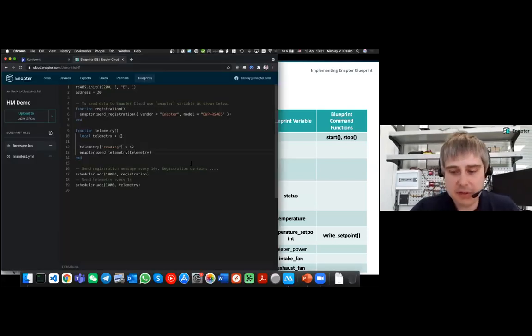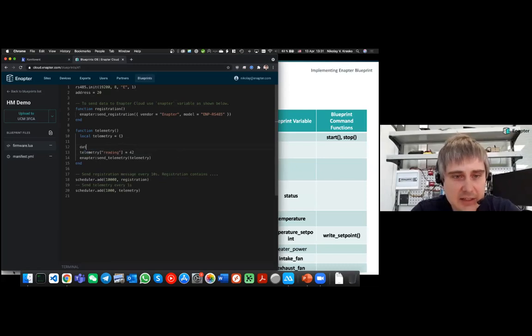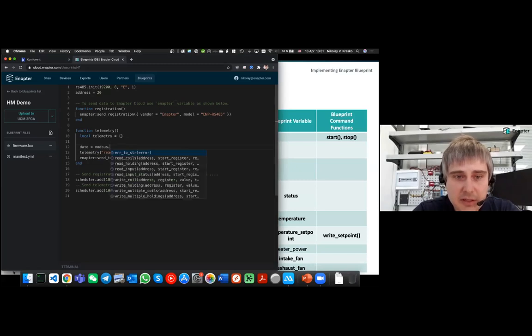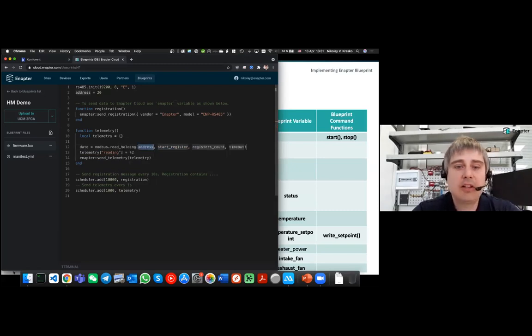So for this purpose, we will declare the table, and we will use the Modbus library and the function called read holding register. The address of our device is located in the address variable declared up in our code. Then we need to put the start register, which is 1100, and we want to read one register. The timeout for this read will be 1 second, so here we put the number in milliseconds.